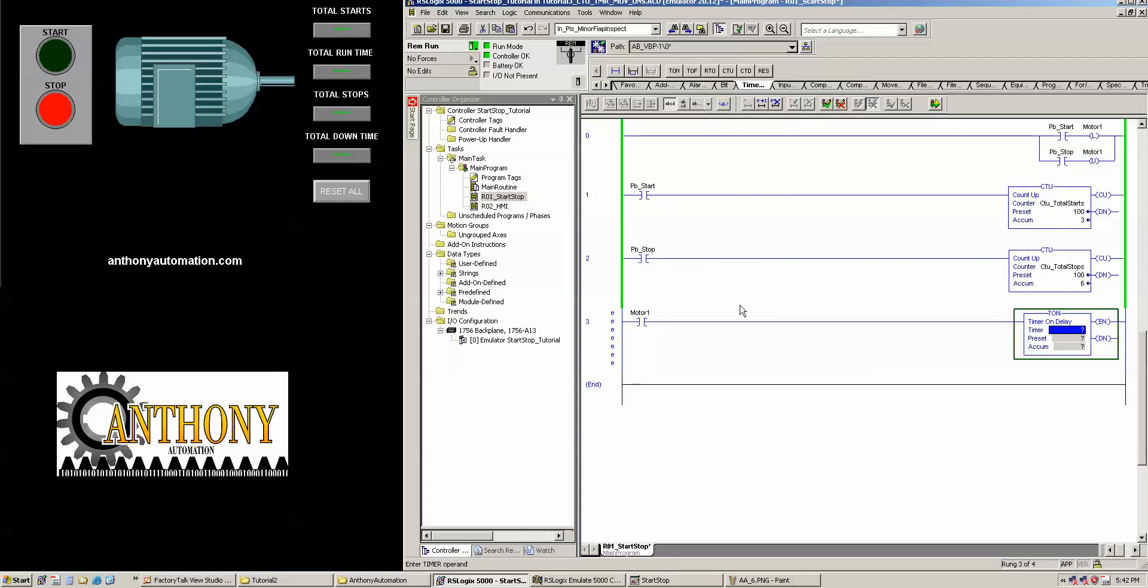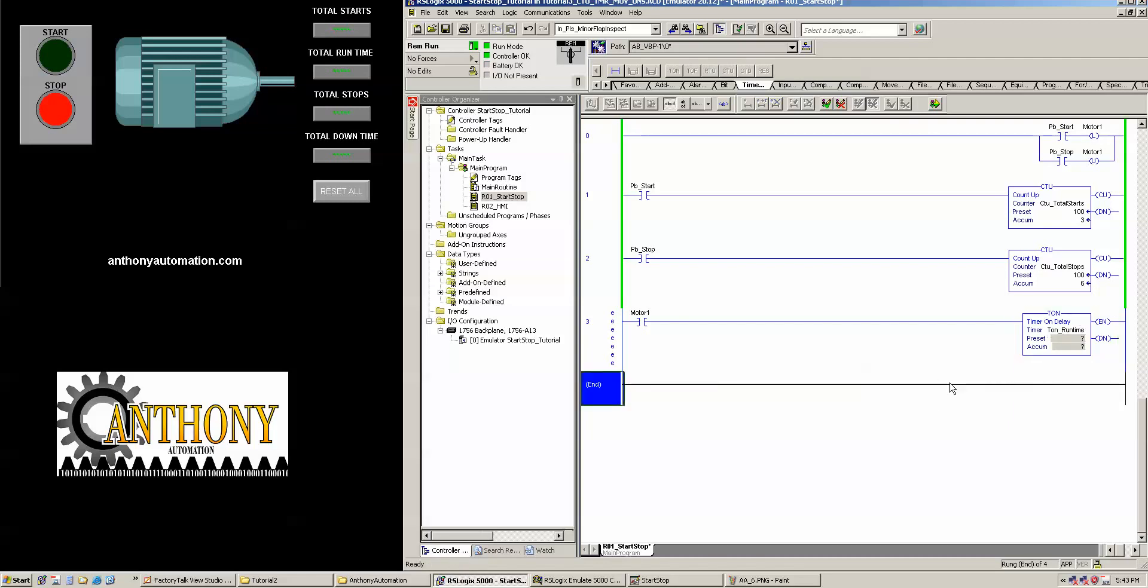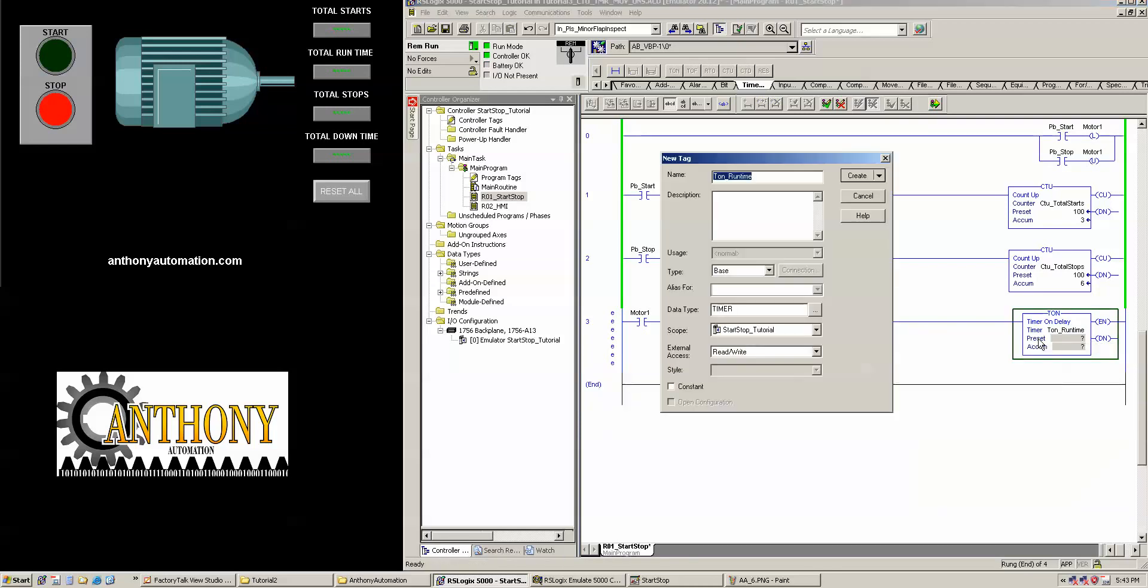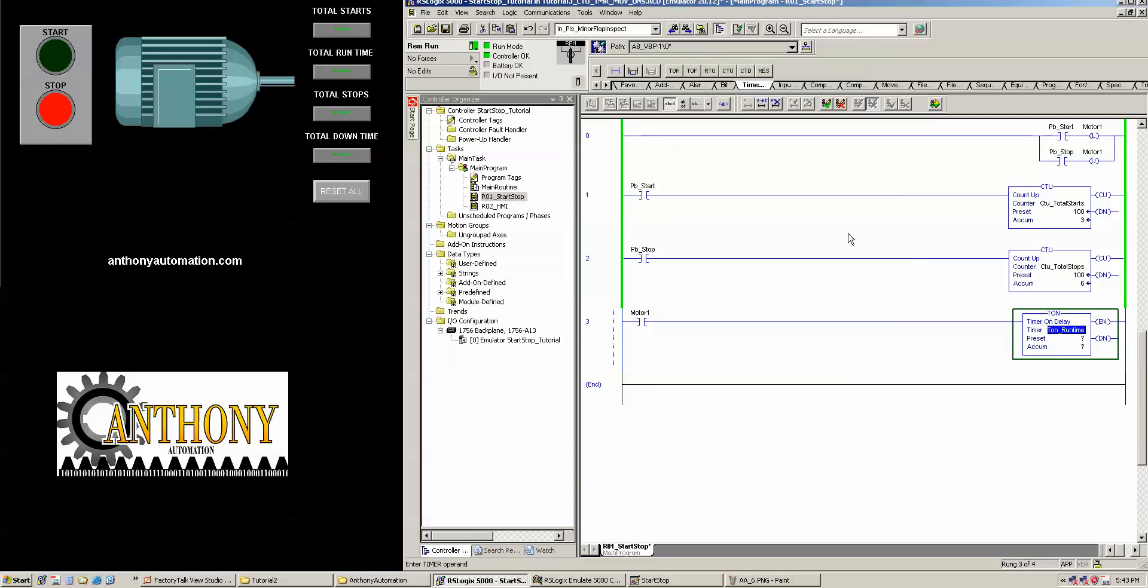And, again, I like to name my, I have to keep the naming convention, T-O-N, runtime. So, we're going to have to name this guy and bring him into the program. And it's a base tag, no alias. Data type is a timer. And it's a global tag. And we're going to set the preset value here to whatever because we don't want it to be done. We just want to know how long it's been running for this particular timer. But you can use timers for all kinds of useful purposes.